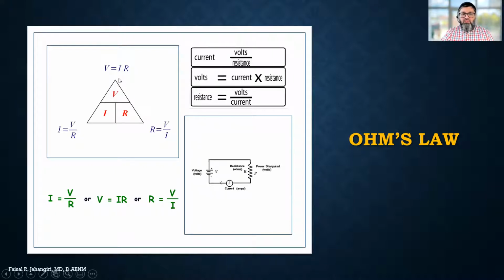If you are doing motor evoked potentials, for example, or using a constant voltage stimulator in any other case, and you see the current is very, very high, that means the resistance is very good. Your placement of the electrode is optimal. If you see low current flow during your motor voltage stimulation, that means your resistance is high. So you need to go and change the stimulation electrode or recording electrode, or use another area where there's better skin contact.